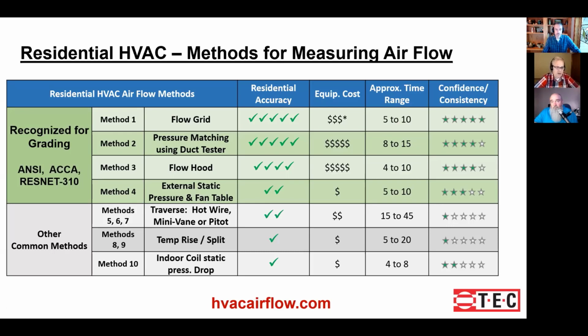If you look at the standards for doing a pitot traverse, they require quite a bit of straight duct, much more straight duct than you would typically have in a residential situation. The other thing is, when a commercial guy is doing a pitot traverse, he's using a really high quality, very accurate manometer. And Brian Orr will tell a story about his first attempt to measure airflow with a pitot tube, and he found out very quickly that his manometer wasn't good enough. Yeah. You just get unrepeatable results and that frustration that Ed talked about.